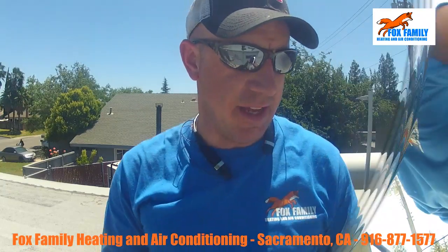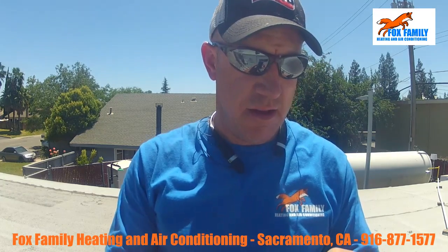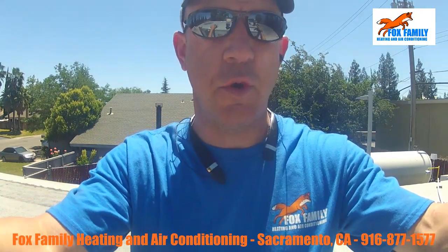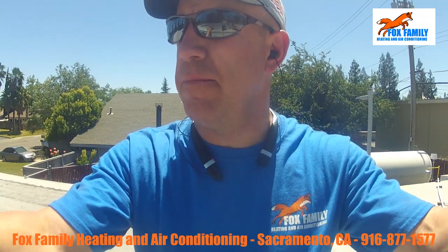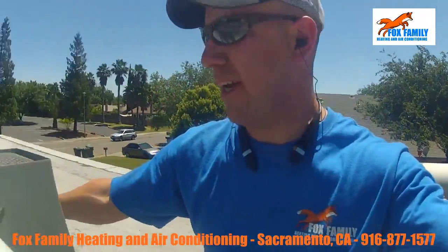Okay, we were able to get this lady up and going now. I thought it was going to be a little bit more intense than that, but I cleaned the evap coil, which was just caked and soaking wet, and it had frozen over, as you saw. Refrigerant pressures look pretty good. I got 73 on the low side, 223 on the high side, which comes out to 110 and 43 degrees, so I'm pretty happy with those.